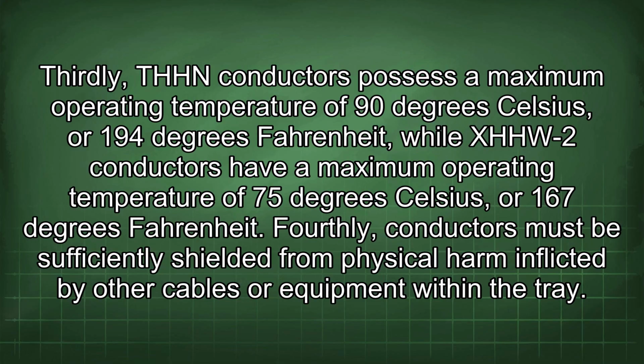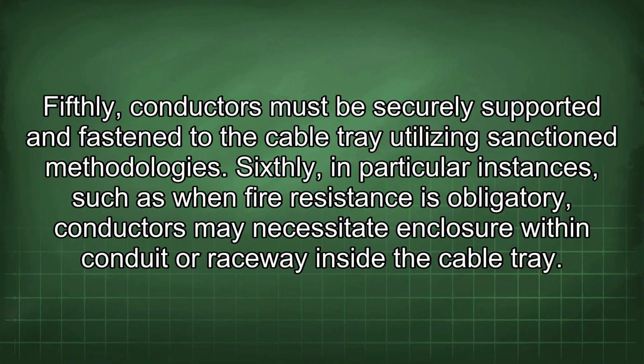Fourthly, conductors must be sufficiently shielded from physical harm inflicted by other cables or equipment within the tray. Fifthly, conductors must be securely supported and fastened to the cable tray utilizing sanctioned methodologies.